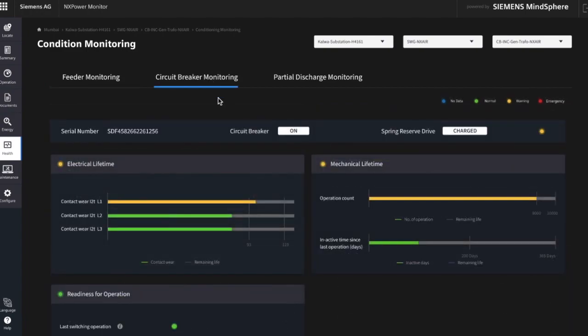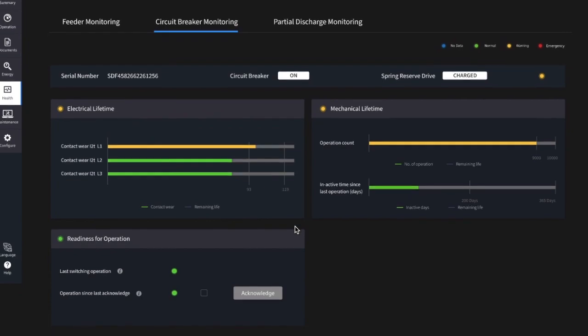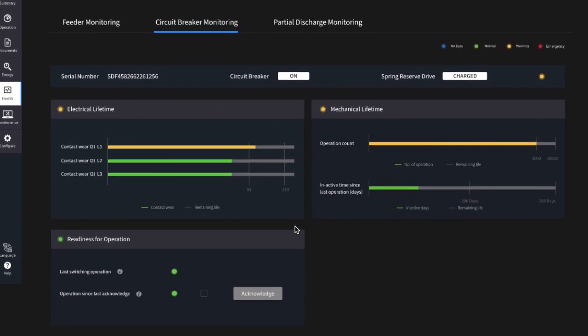In the circuit breaker monitoring view, you get the overview regarding the position of the circuit breaker as well as the spring reserve drive at the top. Additionally, you see three charts which give you insights into the electrical lifetime via I²T-values monitoring, operation counter monitoring, and inactive time monitoring and readiness for operation.